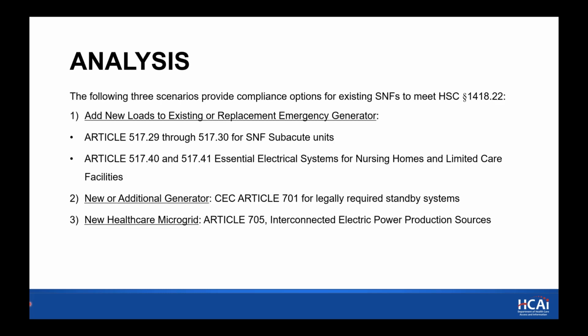Next slide, please. So we've put together 3 scenarios that we see could be followed to show compliance. The first one is going to talk about adding new loads to existing or a replacement emergency generator. So that would be a 517 solution. The second would be a new or additional generator, which would be CEC Article 701, which could be configured as a legally required standby system. And the third option would be a new healthcare microgrid, which would follow the requirements for Article 705. Next slide, please.